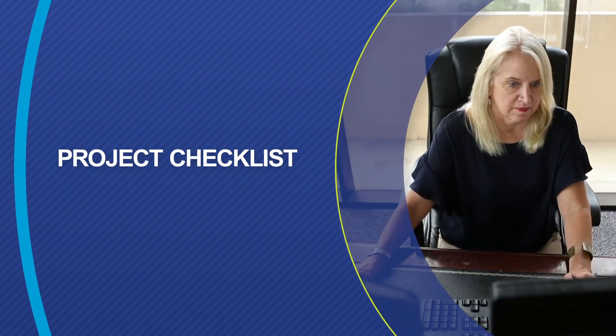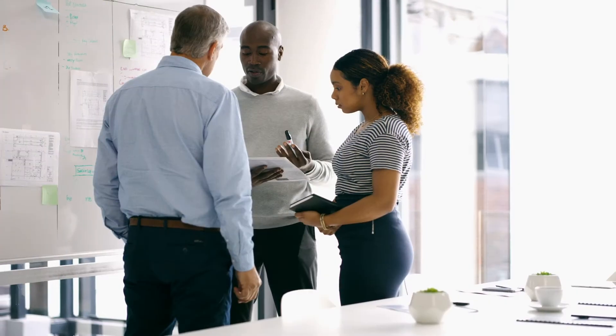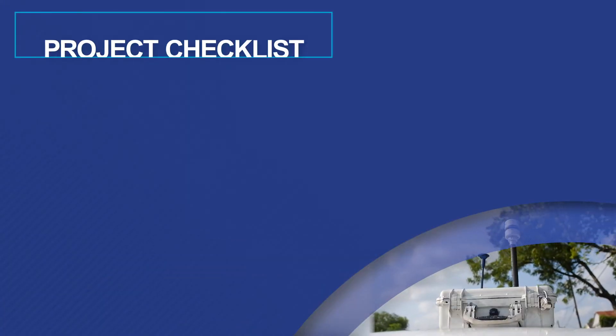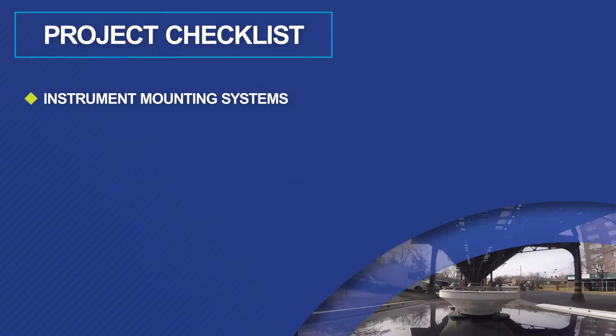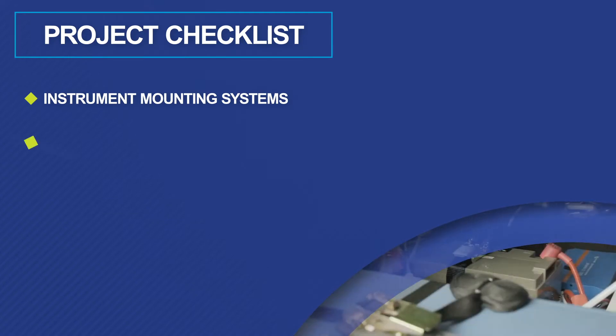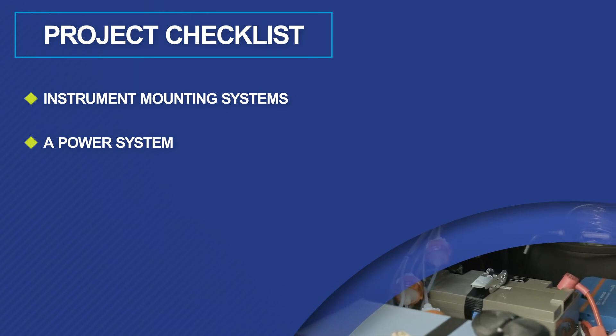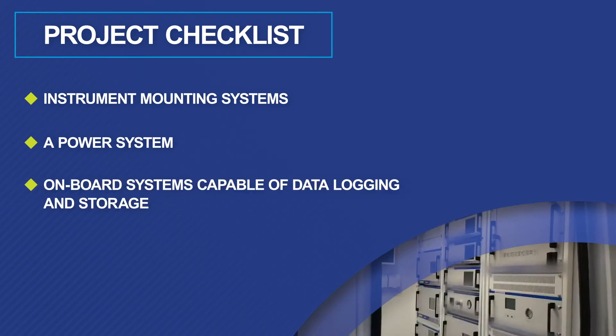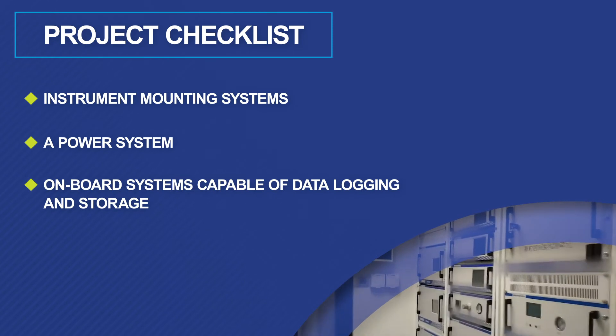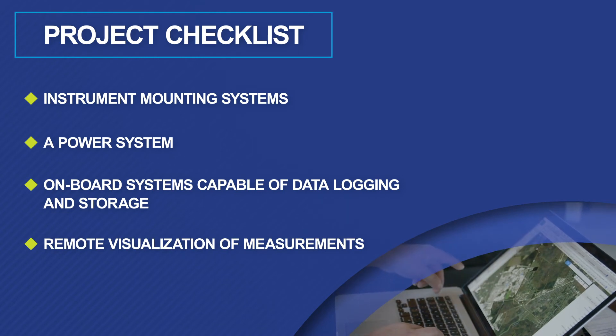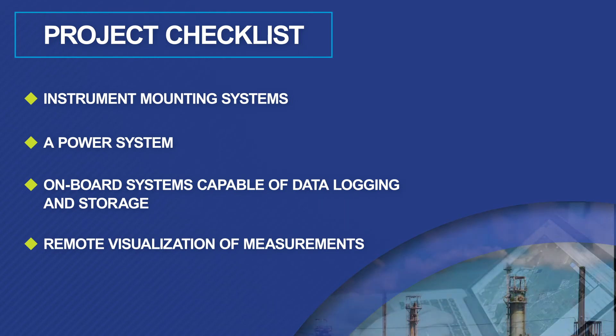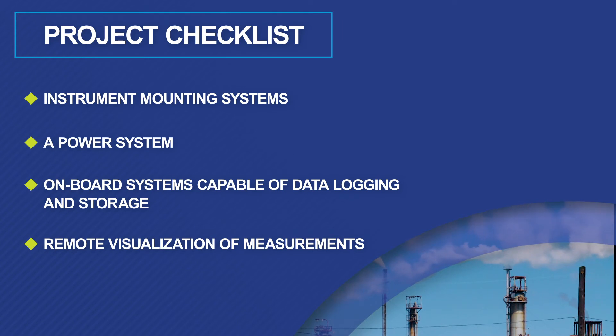Once you decide which vehicles to use as mobile monitoring platforms, there are many project-specific details you'll need to consider. Is the instrument mounting system built to dampen vibration, and is it weatherproof so that it supports the required driving patterns? What about the power system — does it run off engine power or backup power supply? Are the onboard systems capable of data logging and storage for multiple instruments? Can you set up remote visualization of measurements to assess whether your instruments are performing as expected? These are key questions to answer for improved accuracy and durability of your design.